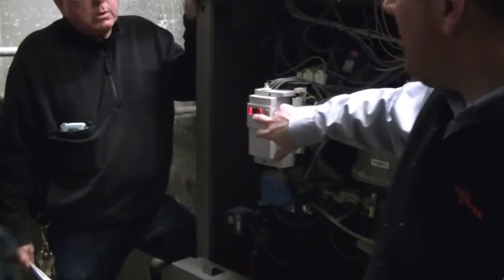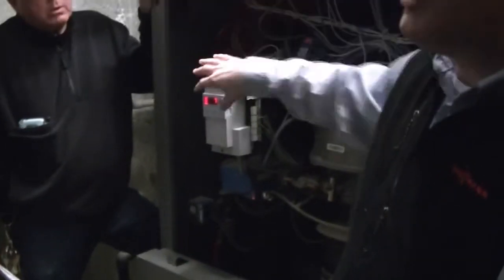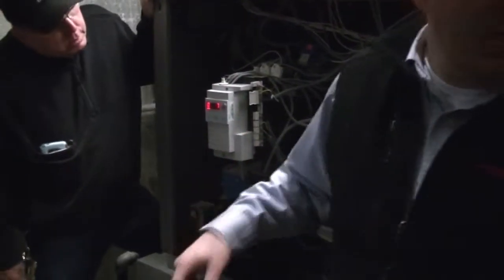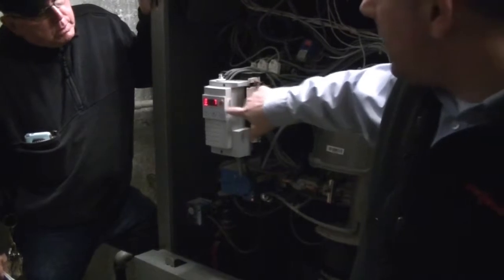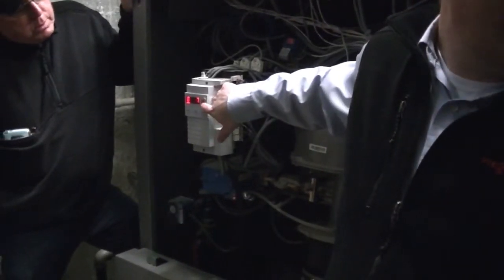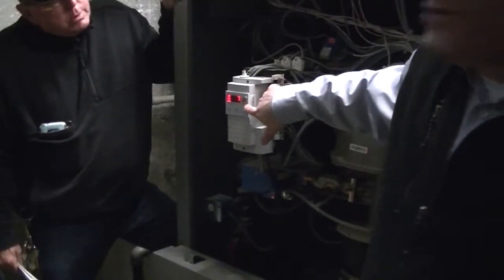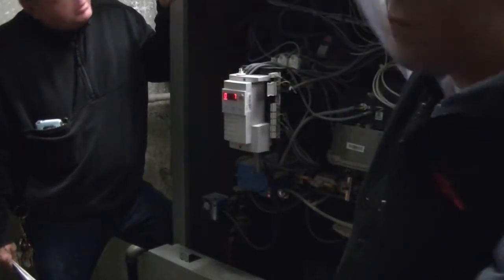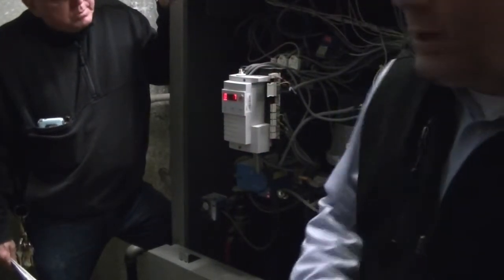Now, we used to have a little opening on the front jacket panel so you could see any faults that come up here, but they now get transferred up to the main control, so you don't need to see this. However, the reset button is on this control if you have a burner lockout. A little red button with the letter R on it, that is your burner reset button. So you'll have a burner fault here, but it'll also show up on the boiler, on the burner up top.